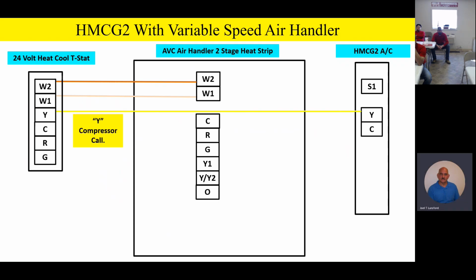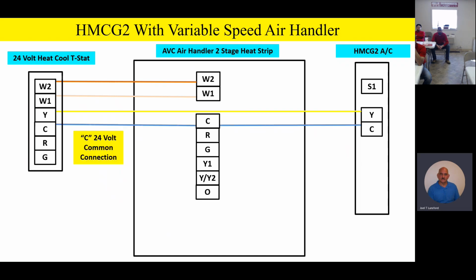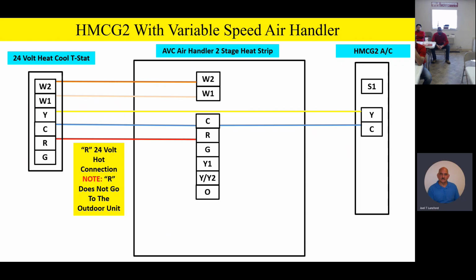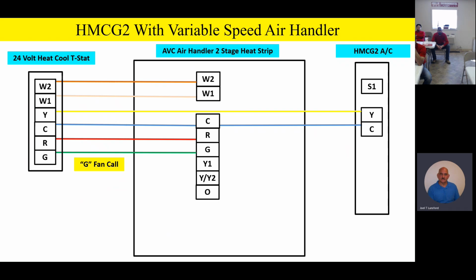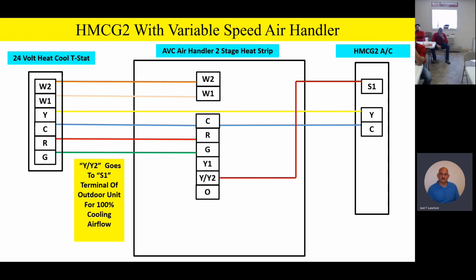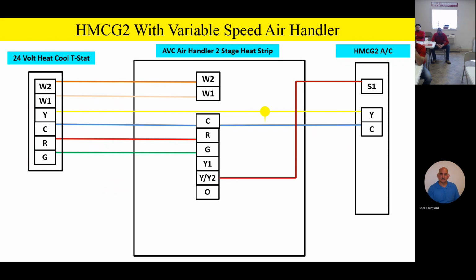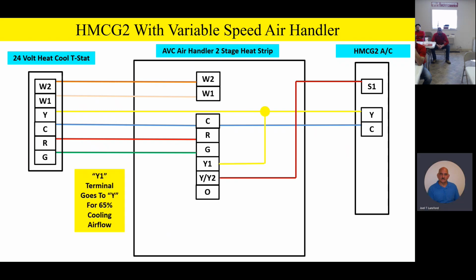Y terminal's your compressor outside, just like before. C terminal goes all the way through, common. R goes from the thermostat to the indoor unit. G goes from the thermostat to the indoor unit. R does not go outside. Y2 is going to go up and grab your S1, just like we had before. Y1, first stage airflow, will be tied onto your yellow wire going outside, so that basically anytime the unit calls for cooling, it'll be at 65% airflow.